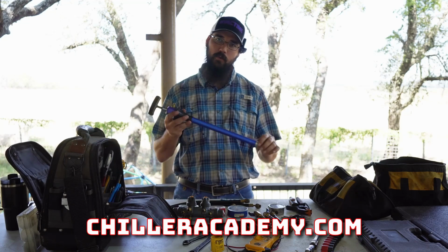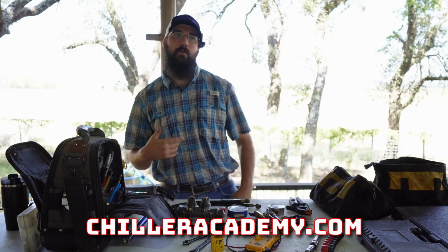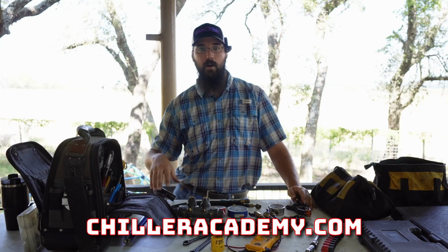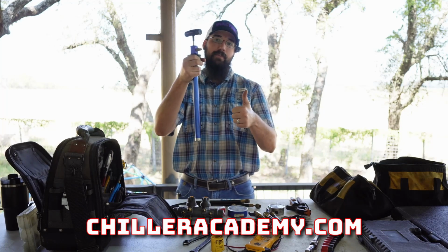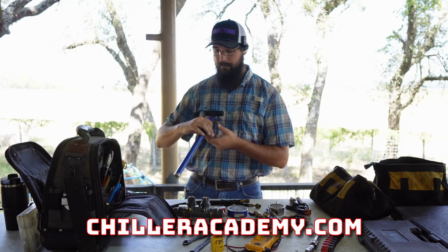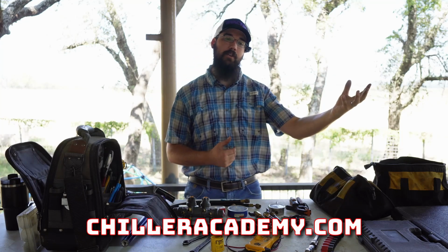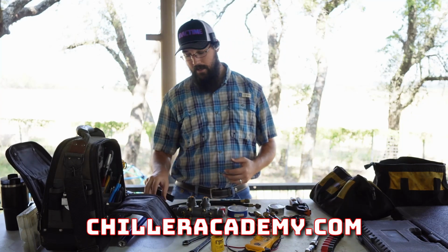Now, these don't work for going the other direction. So if we need to remove oil from the machine and say this is a low pressure, getting it to drain may be an issue, okay? Now there are other ways of doing that. You can pressurize the machine. There are procedures where you don't require a pump, but there's another pump on the market that's like a little foot pedal pump, but it's got a flare fitting on the intake, where this is the intake for this pump here. Those have a little flare. What's nice about those is they're really useful if you have, let's say, a low pressure and you can't use the system pressure to push all the oil out, then you can draw it out with that other style of pump.